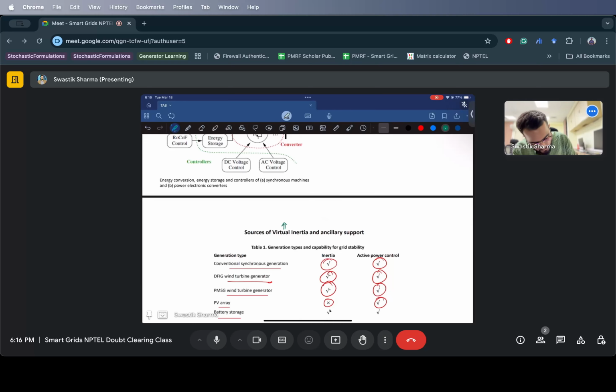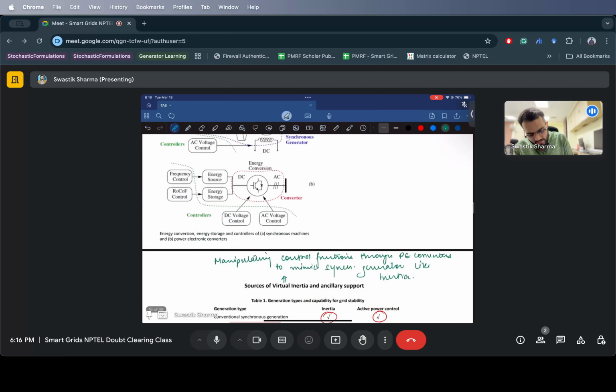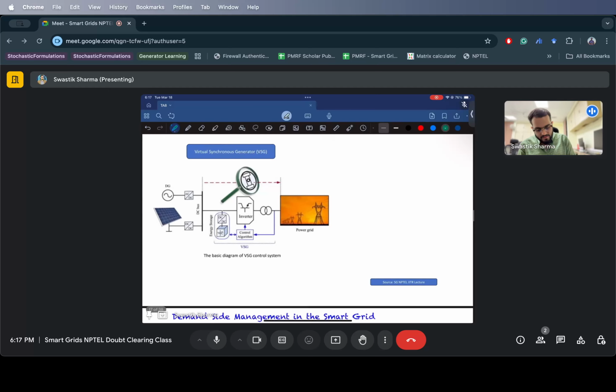So what you do is manipulate the control function in such a way that it behaves like it has some inertia, like a synchronous generator's inertia. So what you need is a control mechanism like Rocof control or frequency control to be able to get virtual inertia out of it. This is one form of a virtual synchronous generator in which you use control algorithms that power an inverter in such a way that you can get inertia out of it.